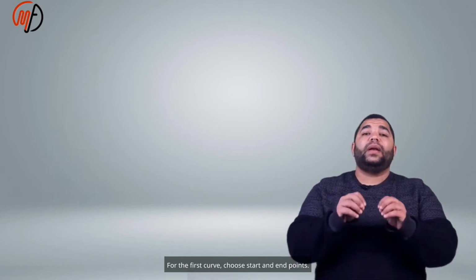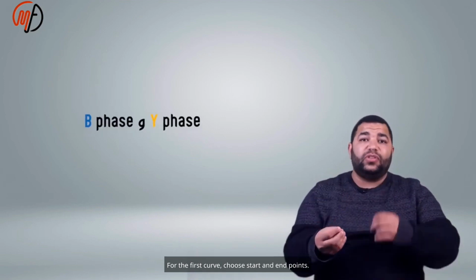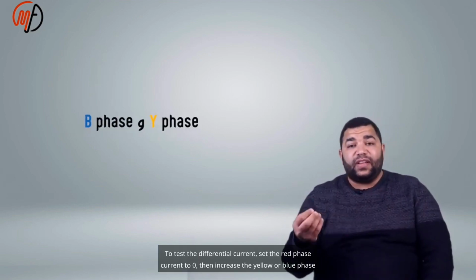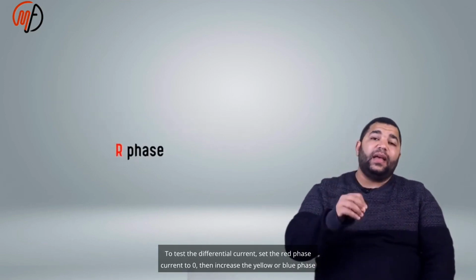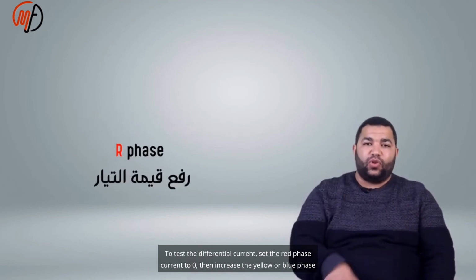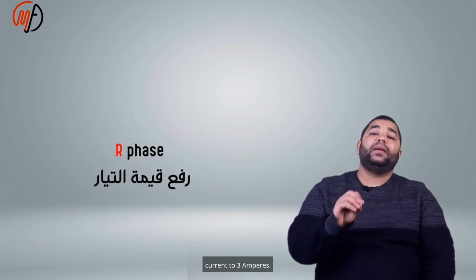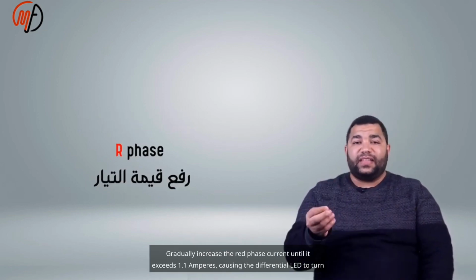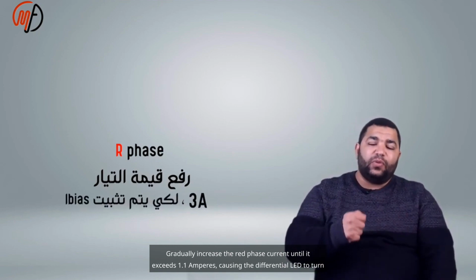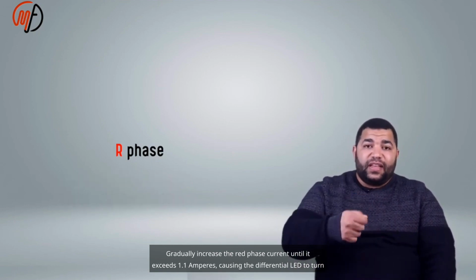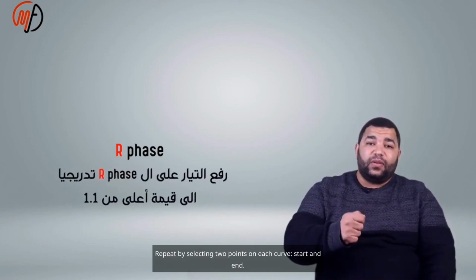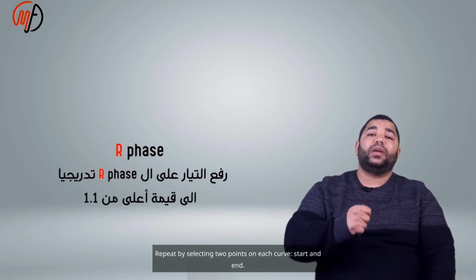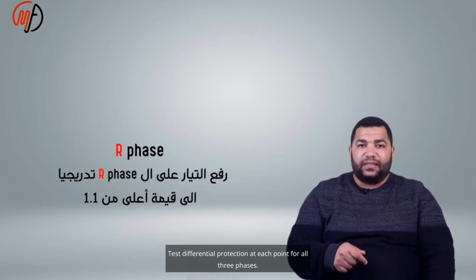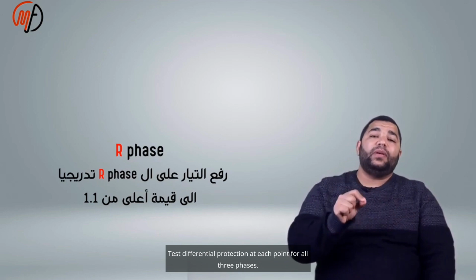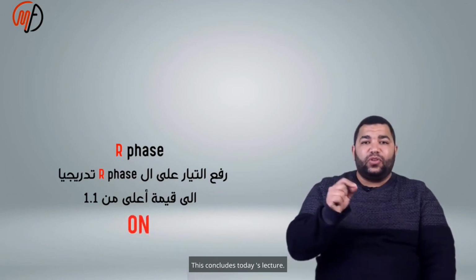Repeat with 2 points on each curve. For the first curve, choose start and end points. To test the differential current, set the red phase current to 0, then increase the yellow or blue phase current to 3 amperes. Gradually increase the red phase current until it exceeds 1.1 amperes, causing the differential LED to turn on. Repeat by selecting 2 points on each curve, start and end. Test differential protection at each point for all 3 phases. This concludes today's lecture.